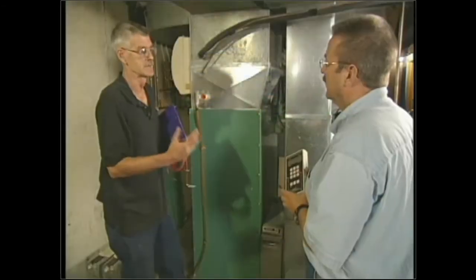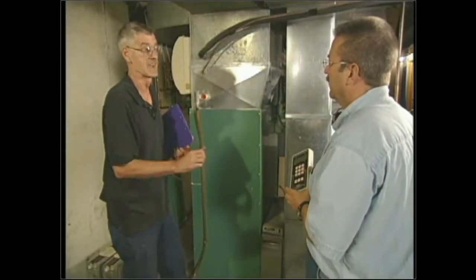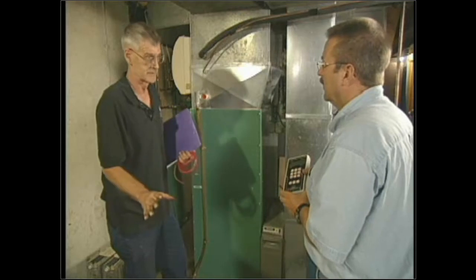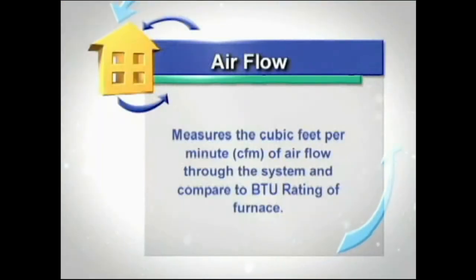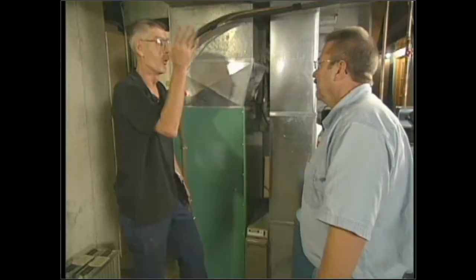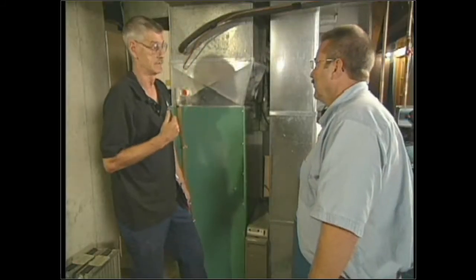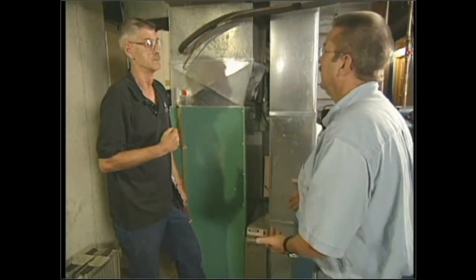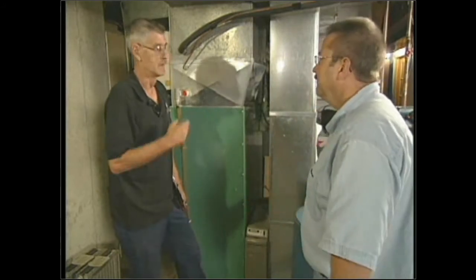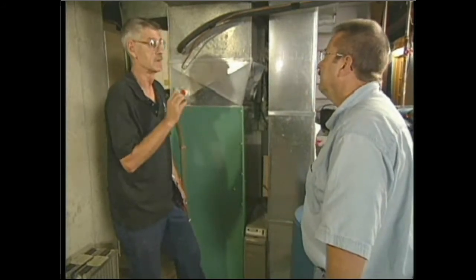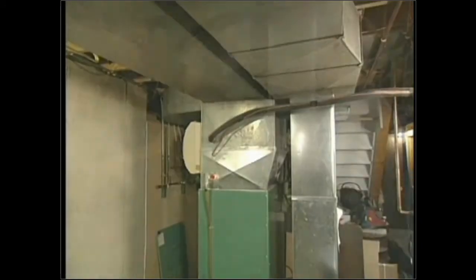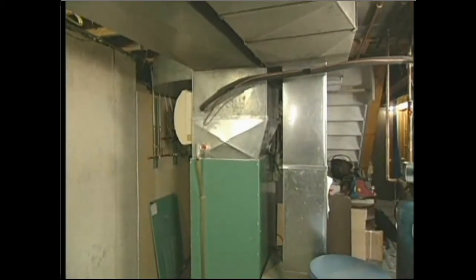The final test we take is a flow meter test. It's taken exactly the same way on all furnaces, whether it's a 70, 80, 90, or an oil burner. It's all the same. And the reason we take this flow meter test is that it tells us how many cubic feet of air per minute this air handler is moving through the whole system, both return and supply. So what we're testing is the CFM of this particular unit, to ensure that we have enough air movement in here so it doesn't cause any damage to the unit. Okay, well, let's walk through that again to refresh our memories.